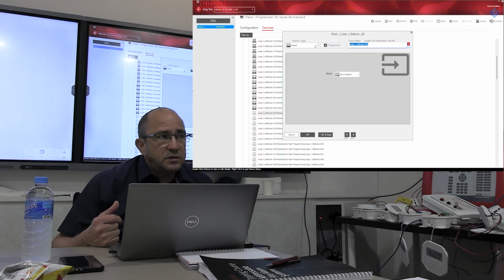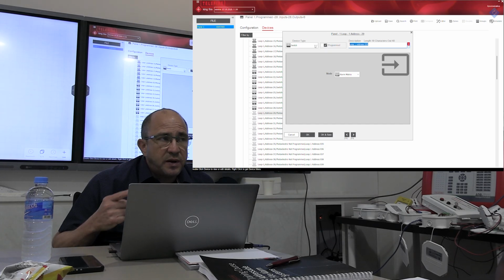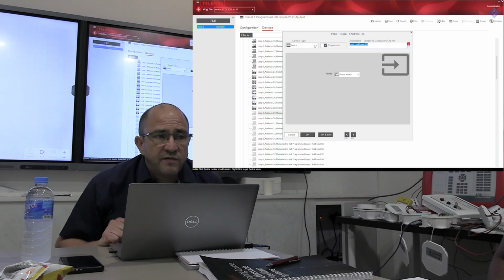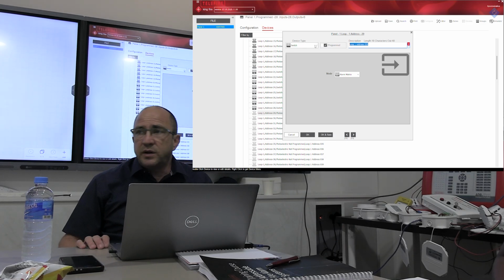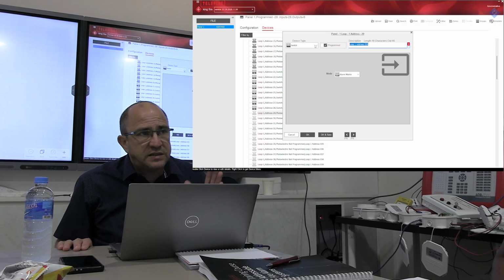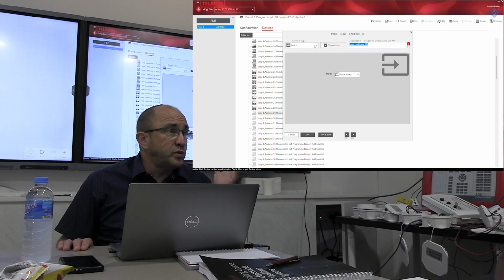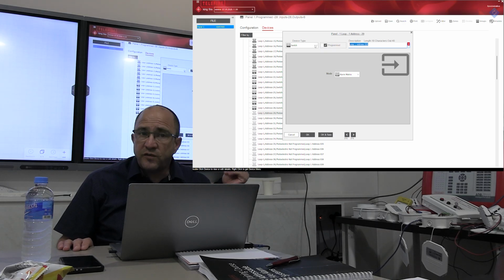You must know this, because this is a powerful tool. It works only on device matrix, not zone and not anything else, only device matrix. If you have that inside and somebody presses that, or a flow switch inside that device, the flow switch will win. It will straight away activate everything.